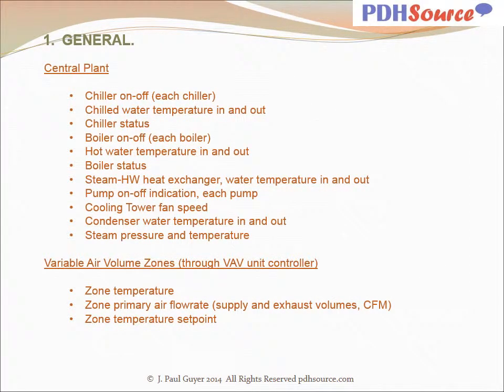For central plants: chiller on-off for each chiller, chilled water temperature in and out, chiller status, boiler on-off, each boiler, hot water temperature in and out, boiler status, steam, hot water heat exchanger, water temperature in and out, pump on-off indication, each pump, cooling tower fan speed, condenser water temperature in and out, steam pressure, and steam temperature. For variable air volume systems, the VAV zones through the VAV unit controller: zone temperature, zone primary airflow, supply and exhaust volumes, zone temperature set point.